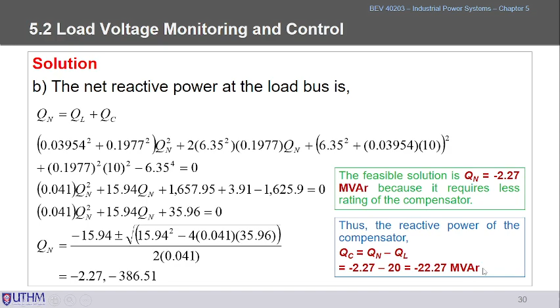We know that Qn is equal to QL plus Qc, so we want to find Qc. Qc is equal to Qn minus QL. Our Qn is minus 2.27, and QL is 20. So what we need to compensate for the voltage loss and voltage drop is an additional minus 22.27 megavar as a compensator.